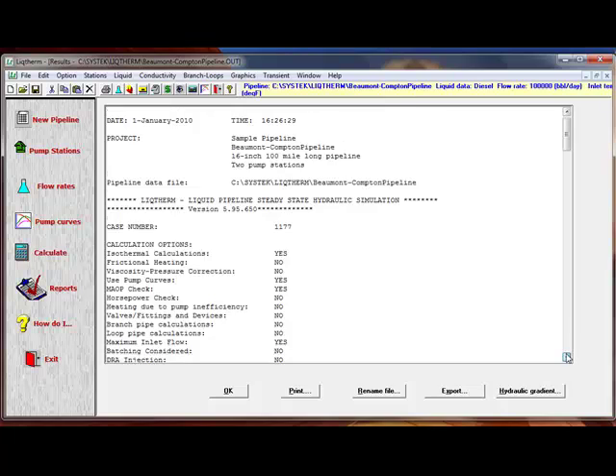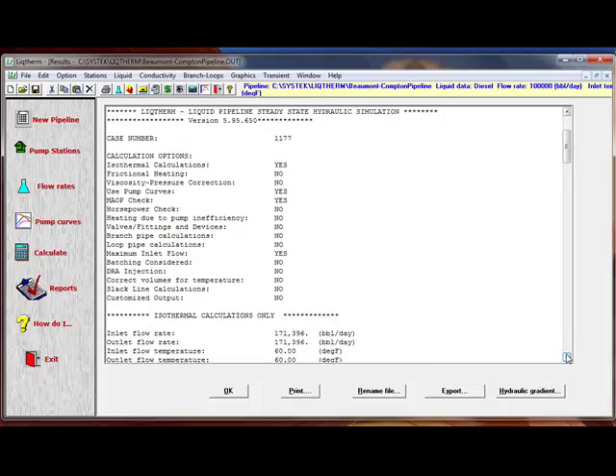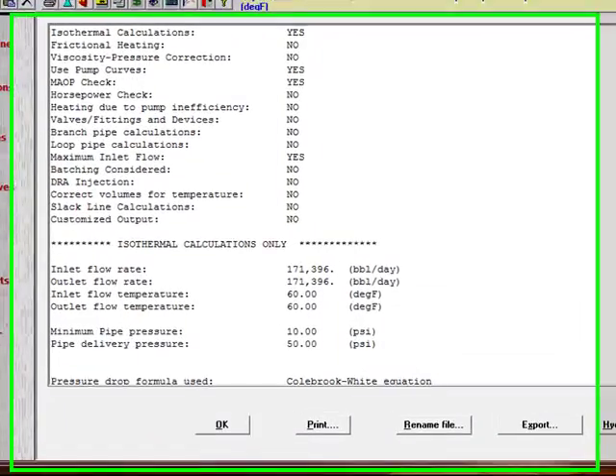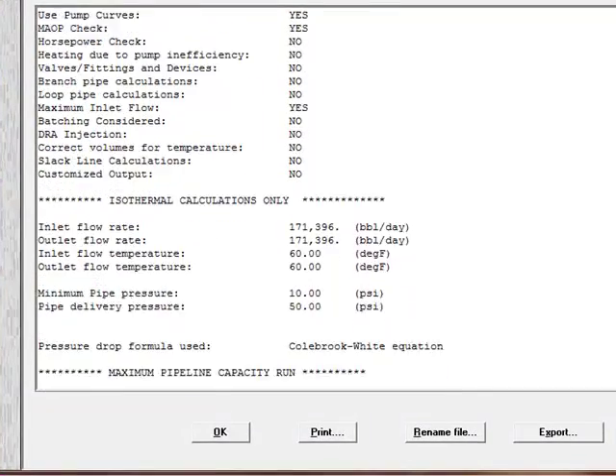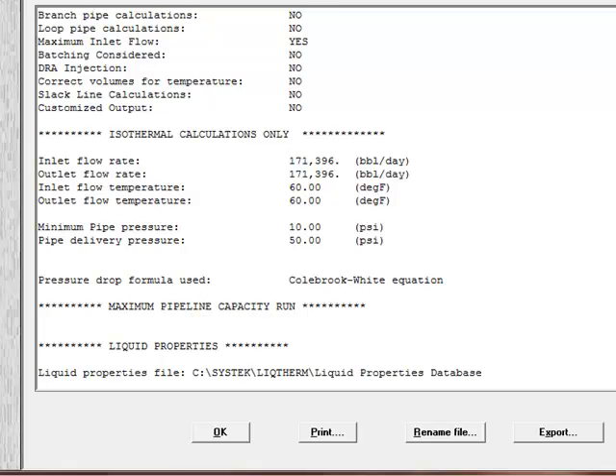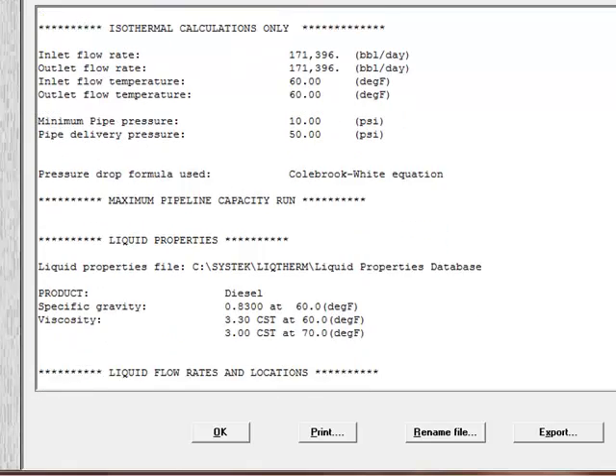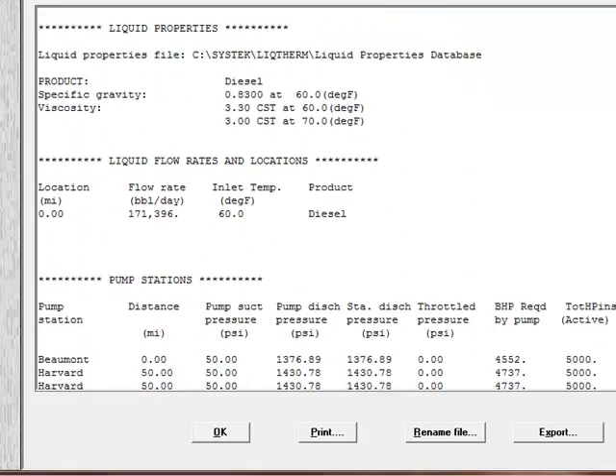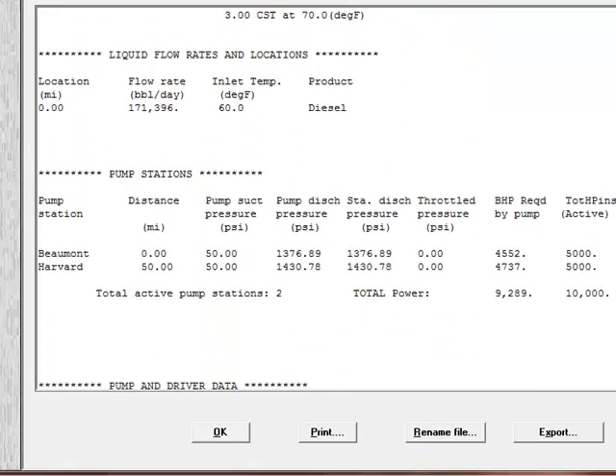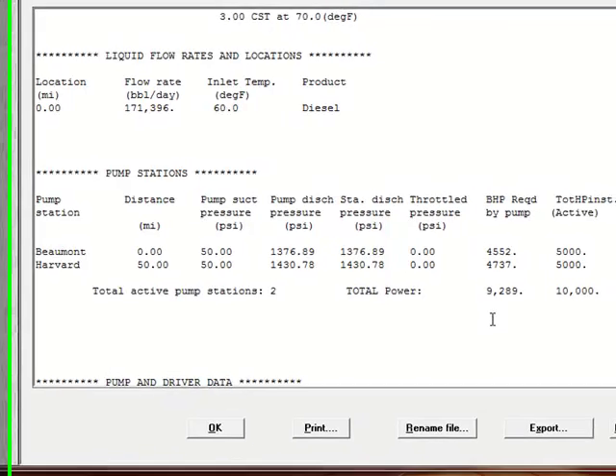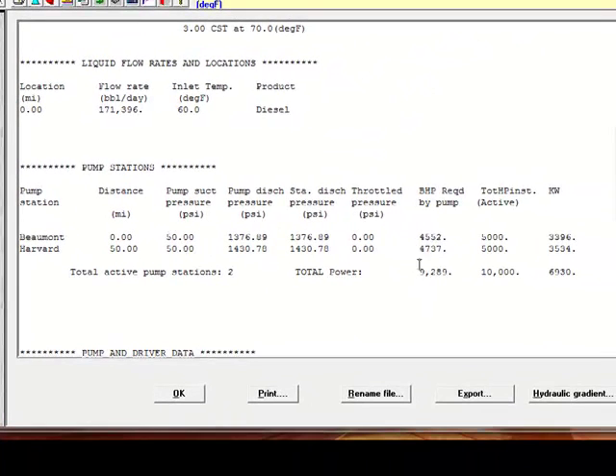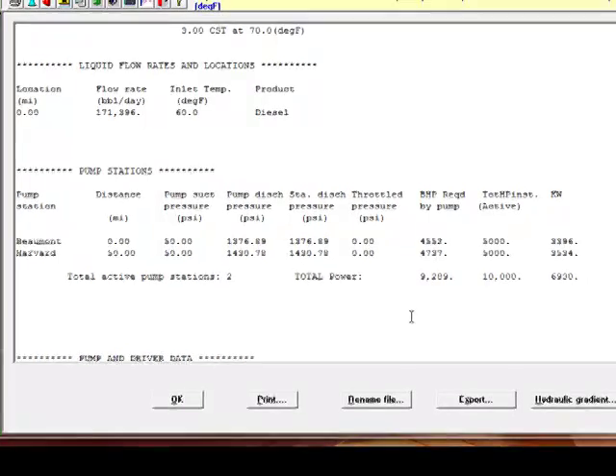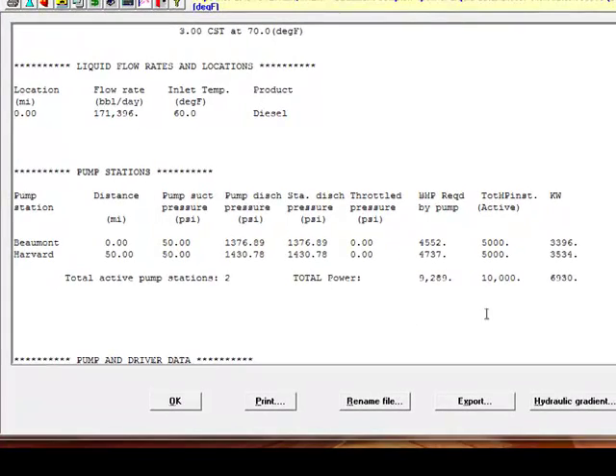The results of the calculation considering the pump curves are again 171,396 barrels per day. In this case, the actual horsepower required based on these pump curves are 4,552 and 4,737 for a total of 9,289 horsepower.